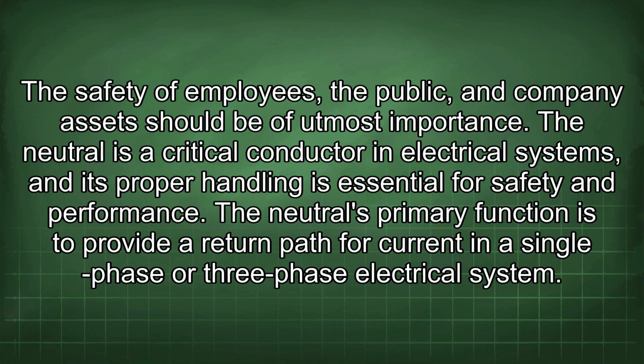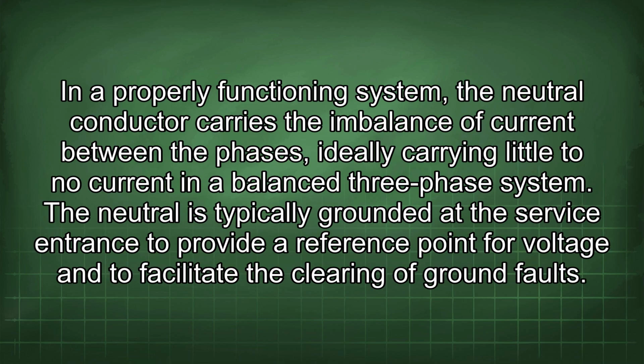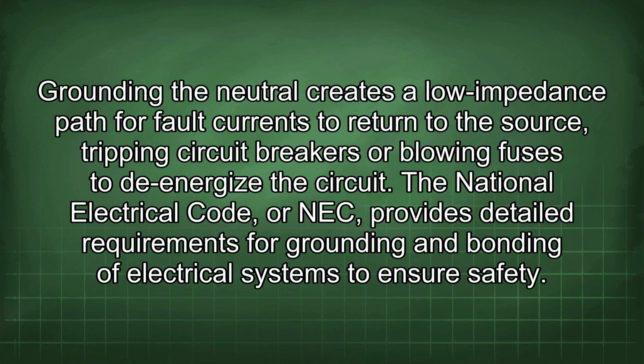The neutral is a critical conductor in electrical systems, and its proper handling is essential for safety and performance. The neutral's primary function is to provide a return path for current in a single-phase or 3-phase electrical system. In a properly functioning system, the neutral conductor carries the imbalance of current between the phases, ideally carrying little to no current in a balanced 3-phase system. The neutral is typically grounded at the service entrance to provide a reference point for voltage and to facilitate the clearing of ground faults. Grounding the neutral creates a low impedance path for fault currents to return to the source, tripping circuit breakers or blowing fuses to de-energize the circuit.